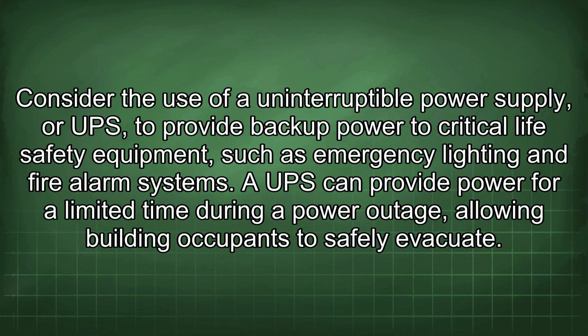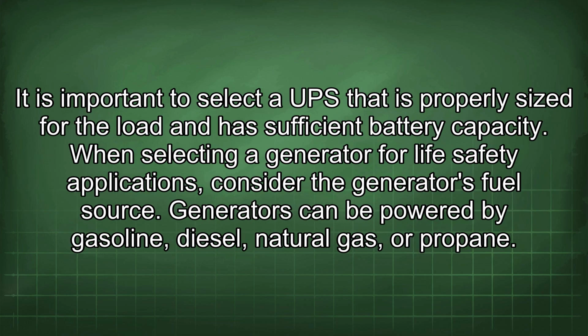Consider the use of an uninterruptible power supply, or UPS, to provide backup power to critical life safety equipment, such as emergency lighting and fire alarm systems. A UPS can provide power for a limited time during a power outage, allowing building occupants to safely evacuate. It is important to select a UPS that is properly sized for the load and has sufficient battery capacity.